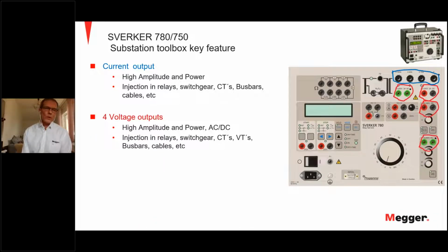It also has 4 voltage outputs. 2 are AC, and 2 of these are DC outputs. And this is also for doing injection in secondary relays, but also to do injection in the switchgear, in the current transformer, for example, to test the current transformer magnetization curve, to find out the voltage knee point, or to test the voltage transformer ratio, for example. So there are a lot of things you can do with these current and voltage outputs from the Sverker 750.